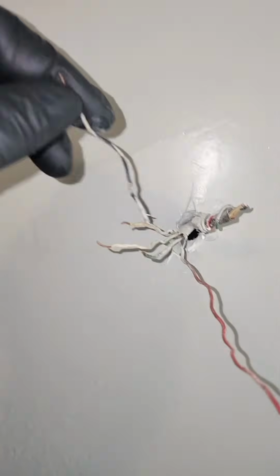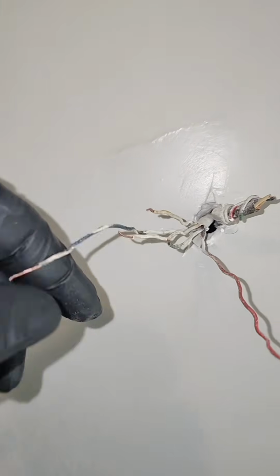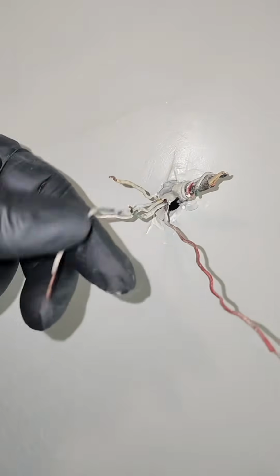So what I'm gonna do, I'm just gonna use common as O for the reversing valve, and then put batteries in the thermostat so that it'll operate. Get as close to the wall as possible. We got a splice right here. That's an 8-wire on the right going to the air handler, and a 5-wire going down to the thermostat.